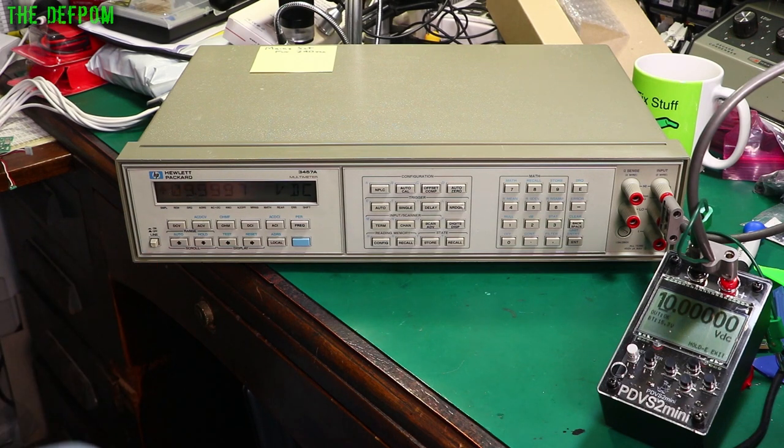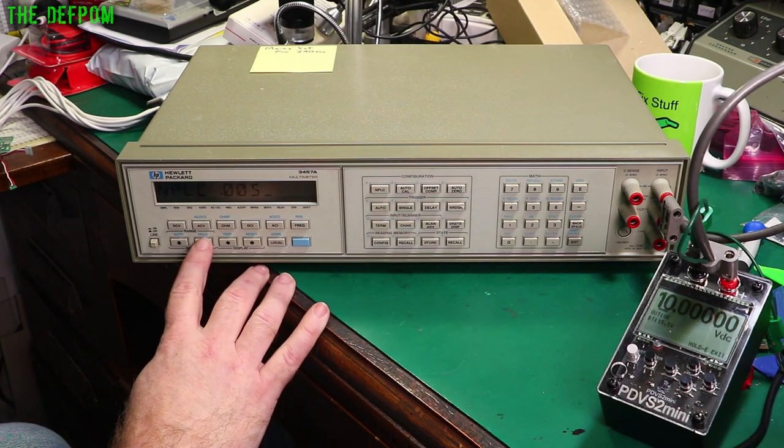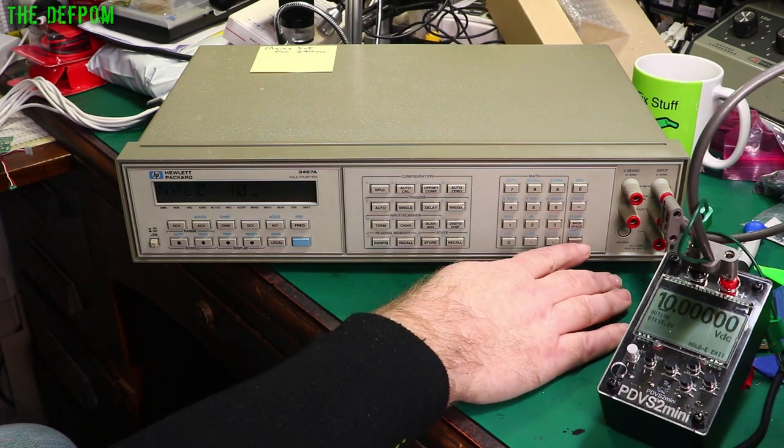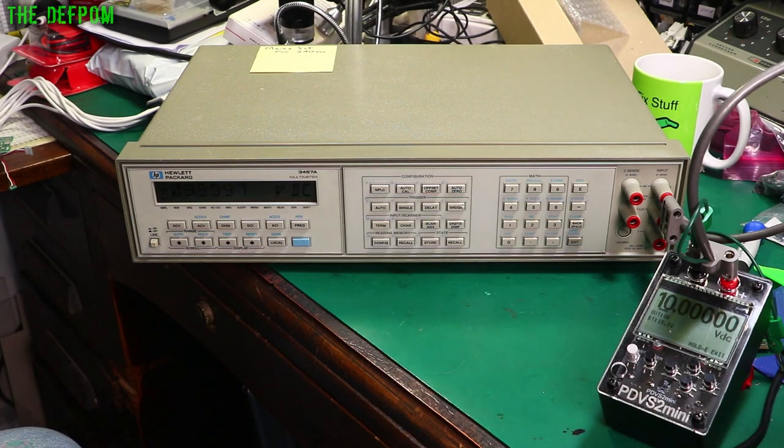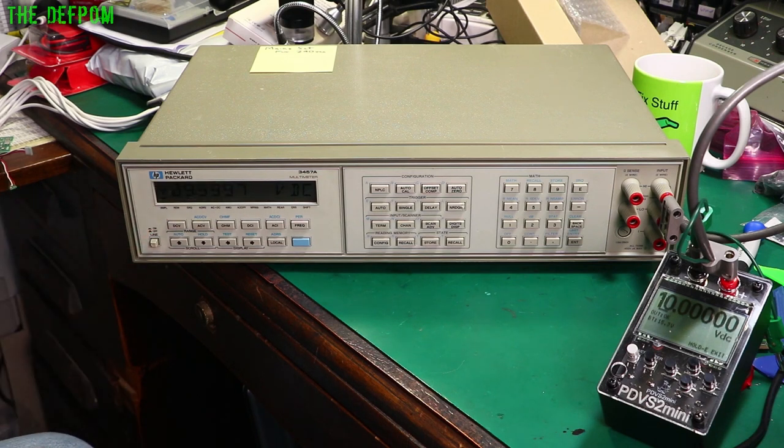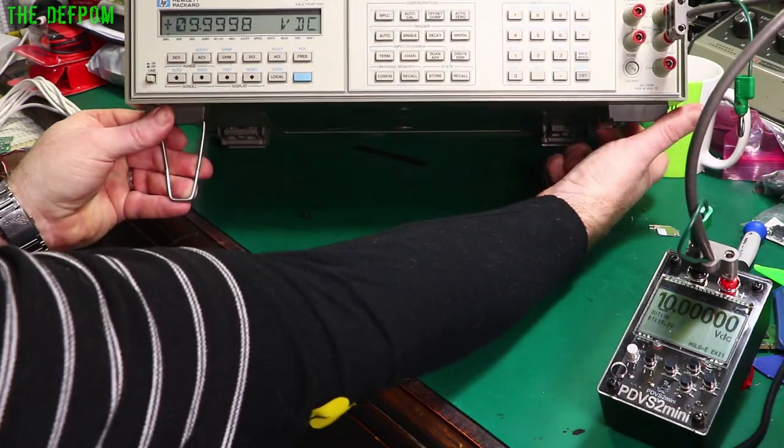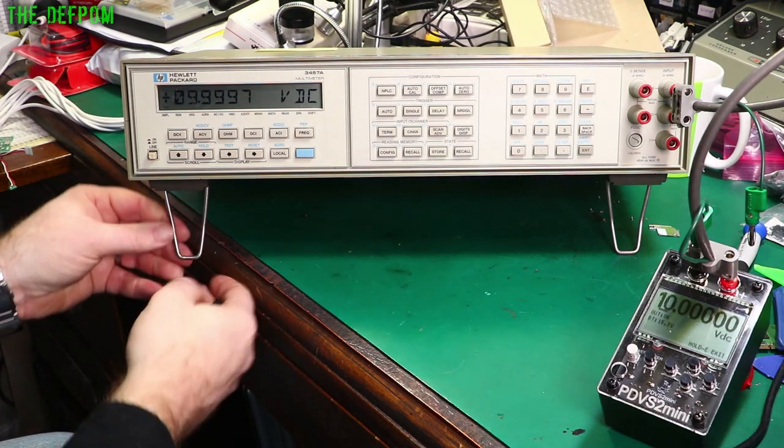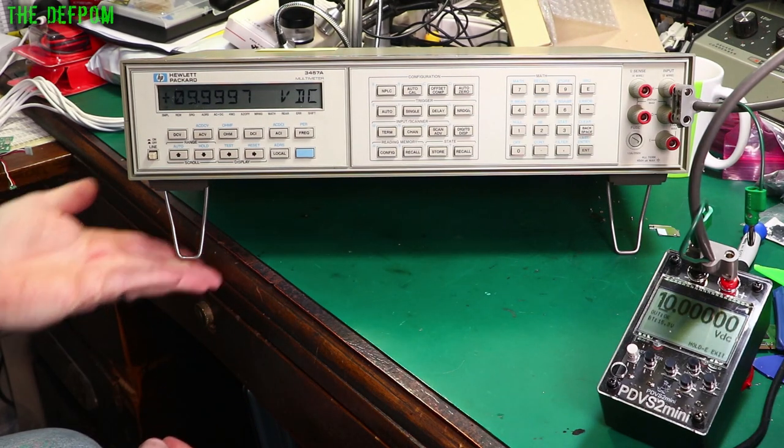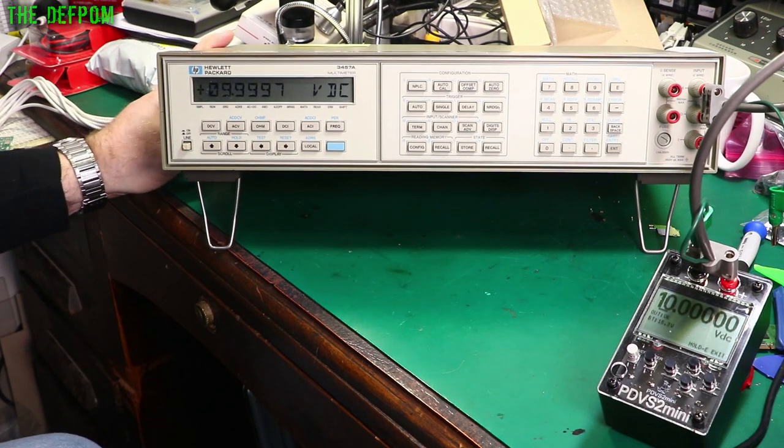And it seems nice and stable. I've set it to 100 power line cycles. I did figure that much out. So you've got PLCs over here and you can change it to what you want through this range. Let's just do 10 for example. That'll be much faster sampling. You can see the sample indicator over here.